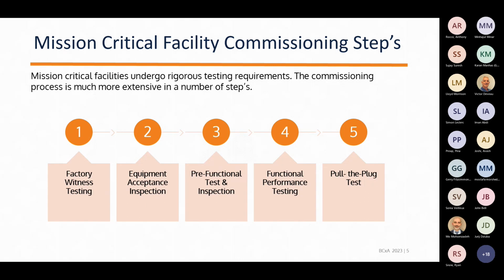Step 5 brings it all together - it's a bit of the grand finale when we get into the testing environment. Basically we do simulation testing, and the main part of that simulation is simulating loss of power and putting that critical infrastructure to work. So you've got generators, chillers, switches, switchboards, automation - checking and making sure all those systems that have been integrated, those multiple paths, are working and communicating. That's the most important step in the functional test process.